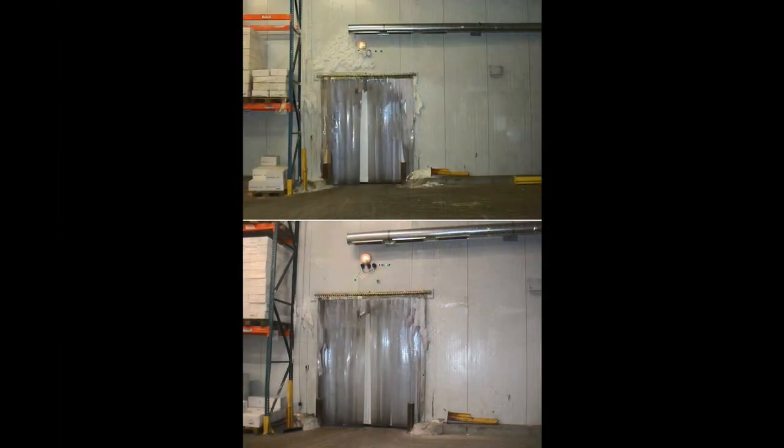And secondly, increased humidity in an environment below zero will result in more ice. So as soon as the moisture in the air hits a cold surface and condenses, it will freeze. And this will typically happen very close to where the moisture enters the room, which is by doorways and entrances. So ice could build up on the walls, ceiling, even on the floor? Yeah, absolutely. And this presents a direct risk to health through slips and falls, or machinery skidding, or simply blocks of ice detaching from a height and falling on somebody. Ice can also stop mechanisms from operating, such as a door mechanism or safety kill switches. And because this happens mainly in doorways, this is where signage often is, where lights are located, or where things like temperature switches are placed, all of which can be impaired with a thick sheet of ice on top.